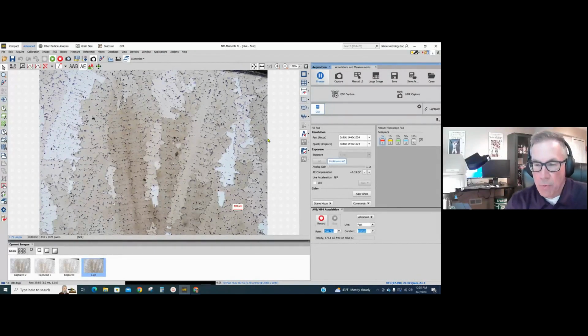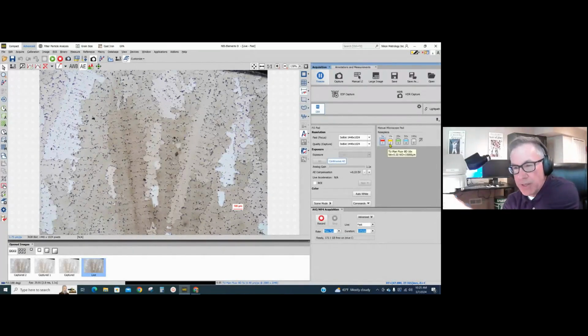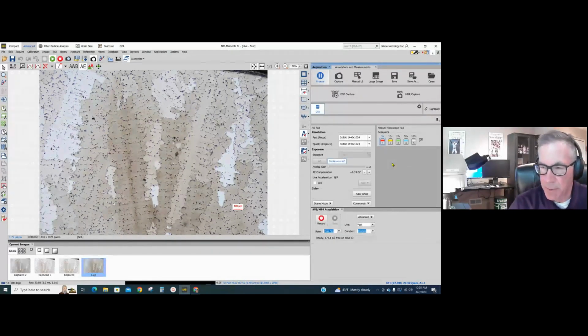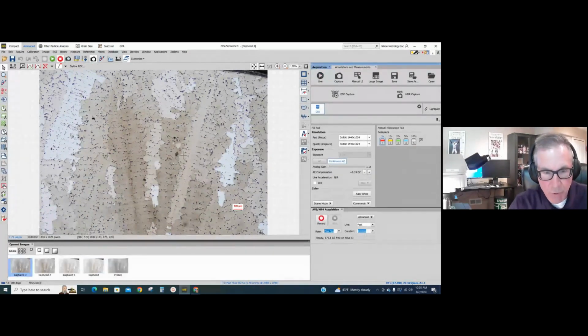So we sell this both ways. If we had our microscope systems with the intelligent nosepiece, as I change my objective, this would automatically change. And that actually is highly recommended if you're going to be purchasing a new microscope. Ask about the intelligent nosepiece. It eliminates mistakes of the person not remembering to check the right button over here. So in this case, capture my image. I've got my scale bar in here.